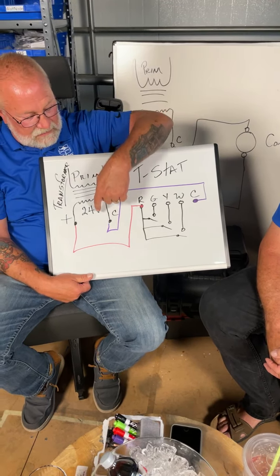Okay, so let me ask you this question. Yes, go ahead, ask me a question. How do you know which one of the wires is the common on the transformer? Well, it's going to be the one not plus. And a lot of the manufacturers will actually take the common and chassis ground it. Yes. Once you ground this one and connect it to common, that's the common side. But a lot of manufacturers don't actually ground their transformers on the low voltage side. A lot of them don't. That's just because they couldn't afford the ground wire. I understand it's small and they got cheaped out. So I'm going to give you that.